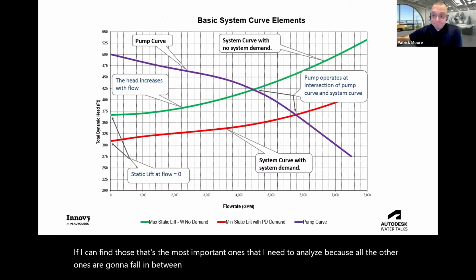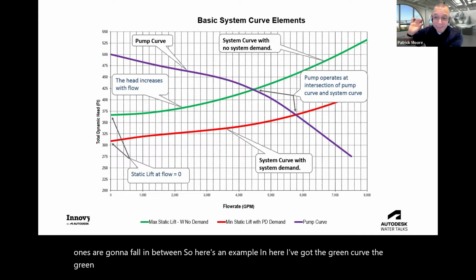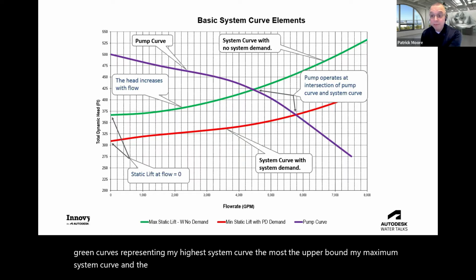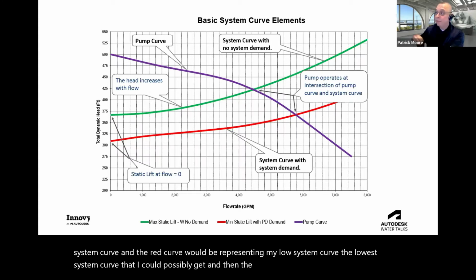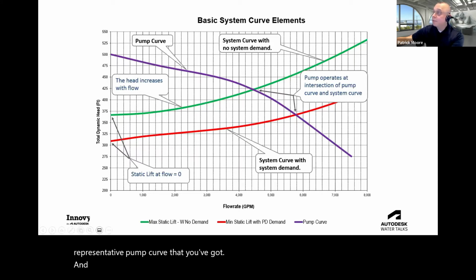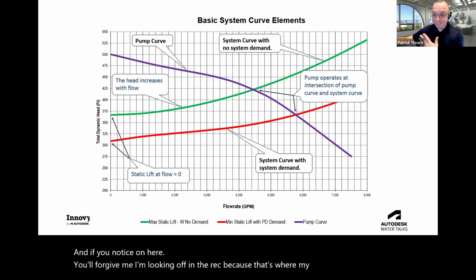So here's an example. In here, I've got the green curve. The green curve is representing my highest system curve, the upper bound, my maximum system curve, and the red curve would be representing my low system curve, the lowest system curve that I could possibly get. And then the purple curve here is basically a representative pump curve that you've got. And if you notice on here, now you'll forgive me, I'm looking off on the right because that's where my presentation screen is, or my camera is right in front of me here.